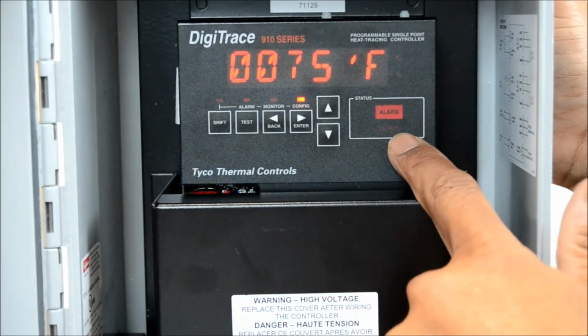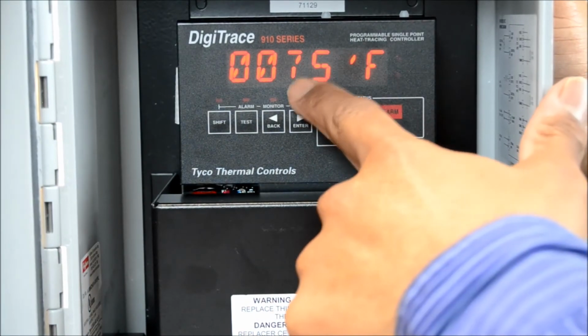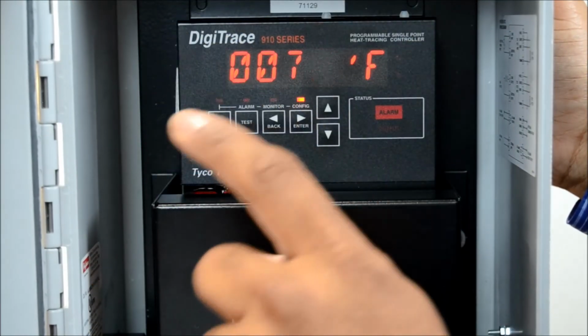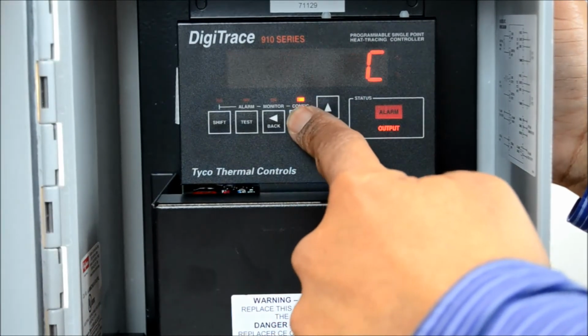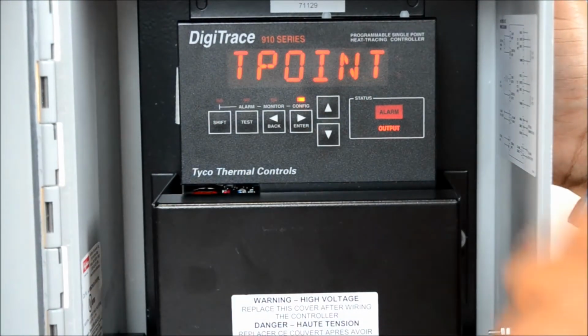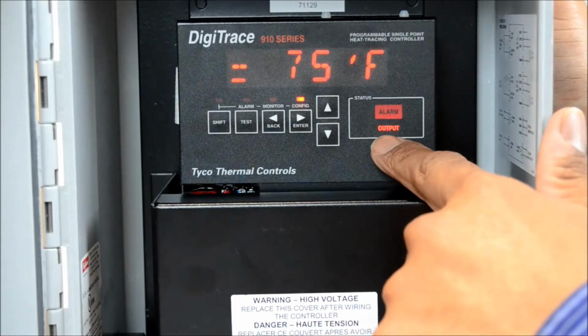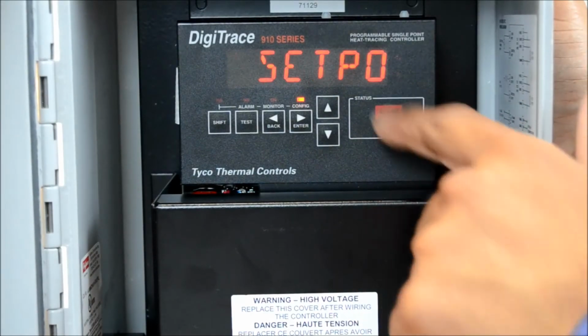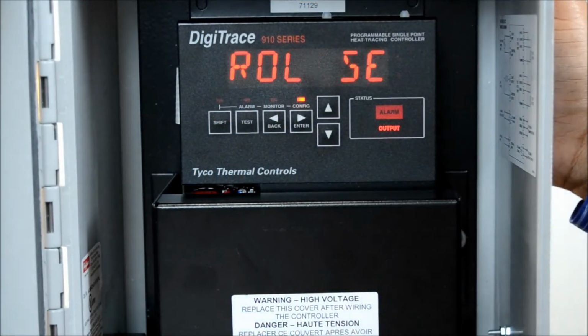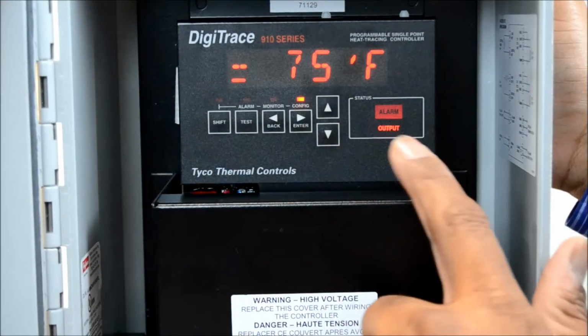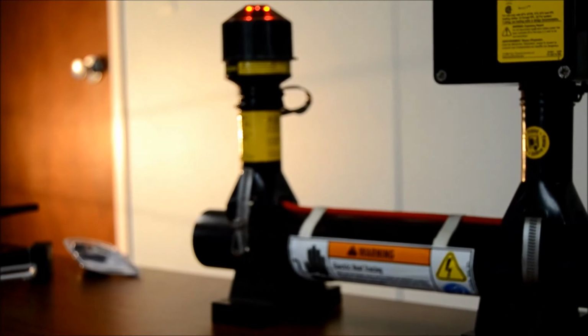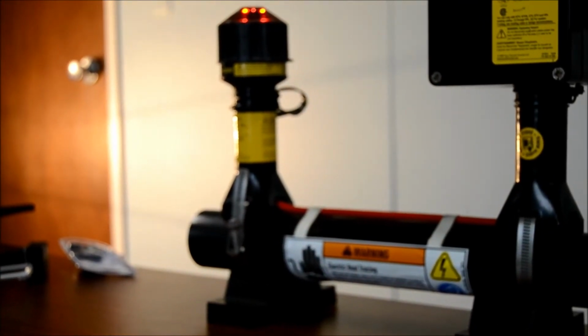Now you notice that the heat trace is not on yet, and this is still blinking. Well, in order to set this, you have to hit Enter. And when I hit Enter, the output light comes on because the set point is now raised to 75 degrees, so the heat trace is working. And I don't know if we can pan over to the light of the end seal, but I have this connected over to the light, and you can see the light on the end seal is turned on now, and that indicates that the heat trace is working correctly.